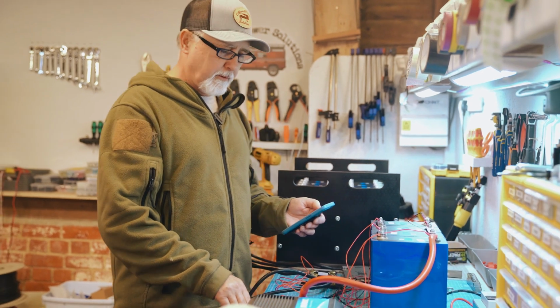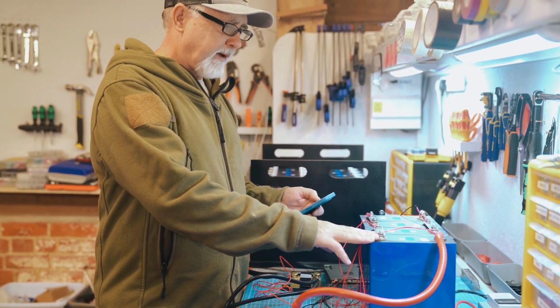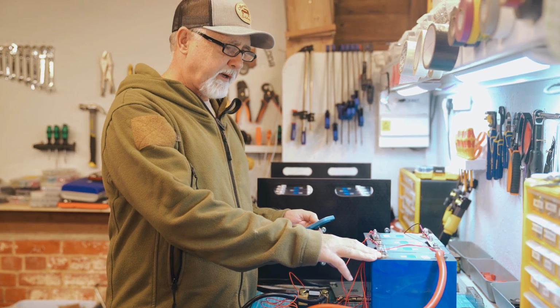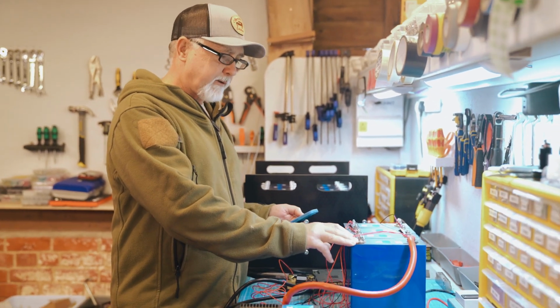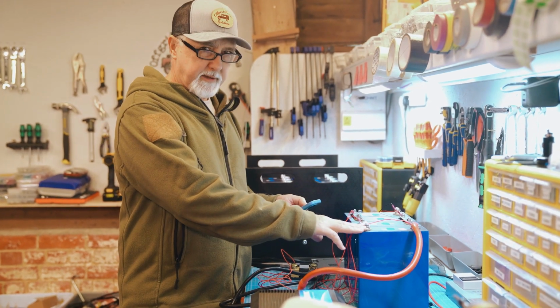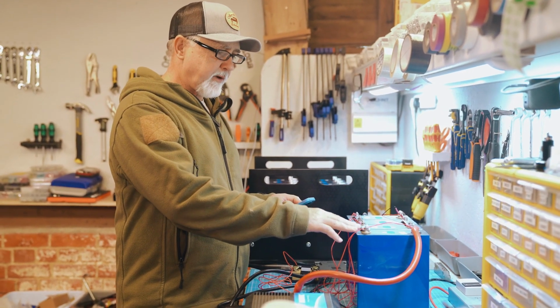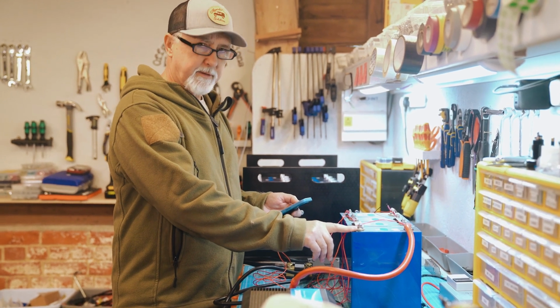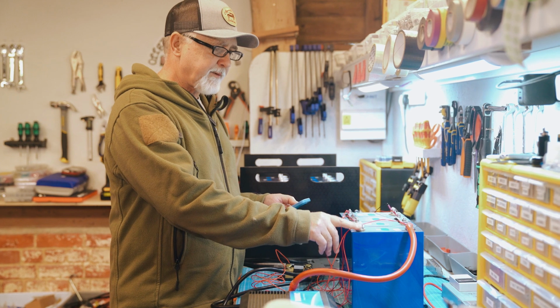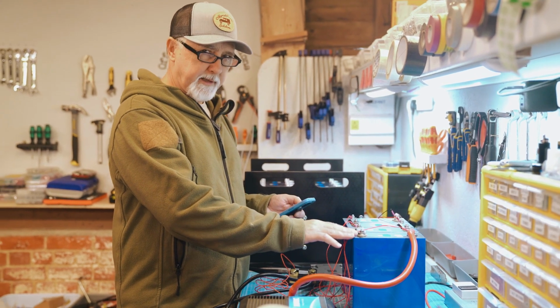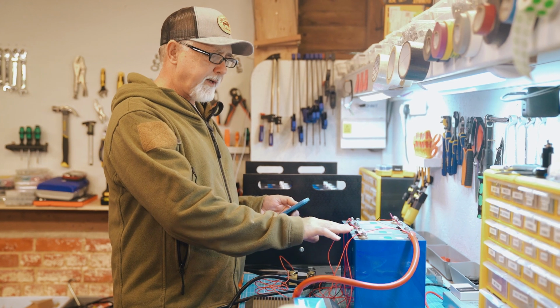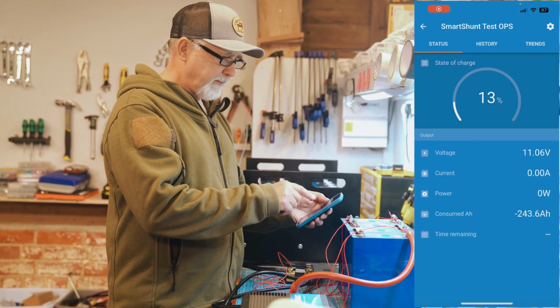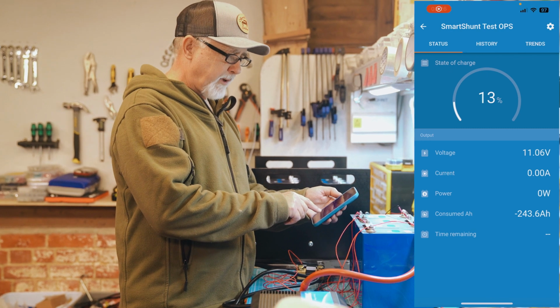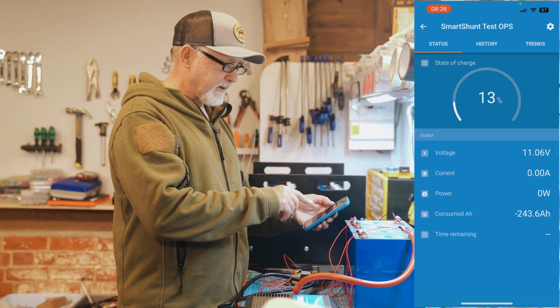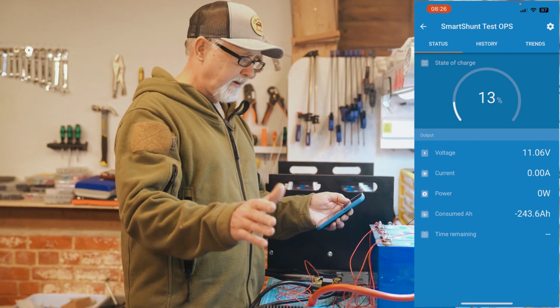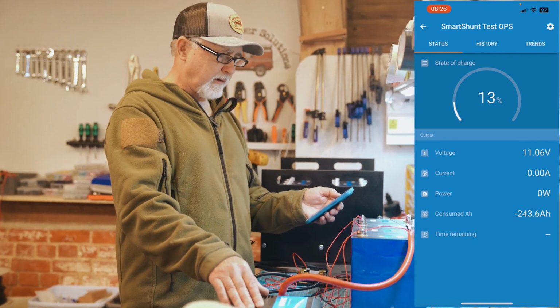Right, we have concluded the test of these cells, and the big question is, would I recommend them? Yes, I would actually, because they have met capacity on the slow burn. So we discharged them individually at sort of 10 amps for a while, 15 amps for a while, and they all met capacity. They exceeded capacity, and they were quite similar to each other, so quite uniform. On the high burn, as you can see, we met 243.6 amp hours before the inverter shut down at low voltage.